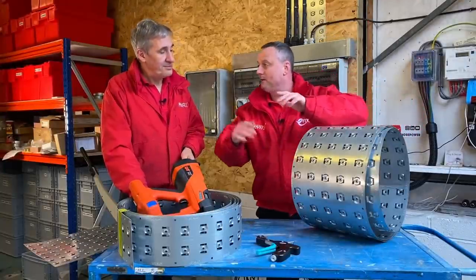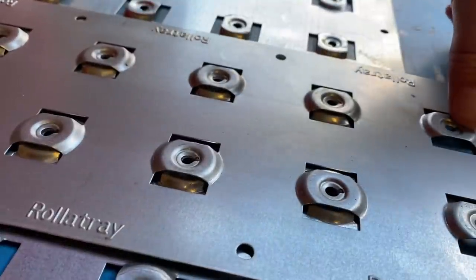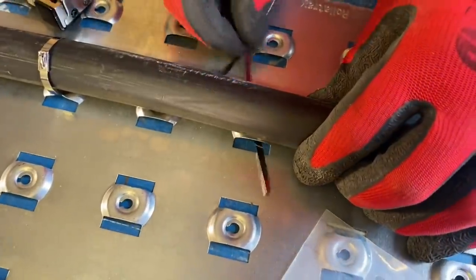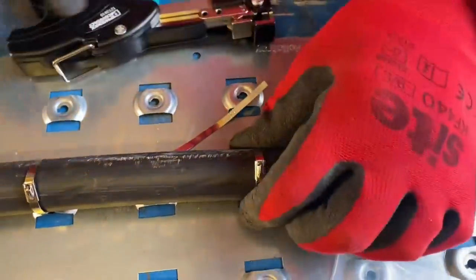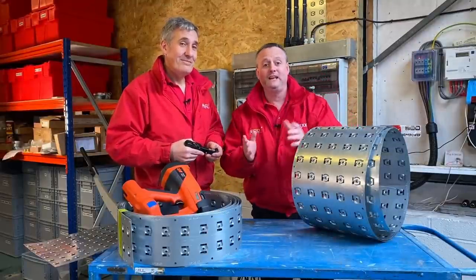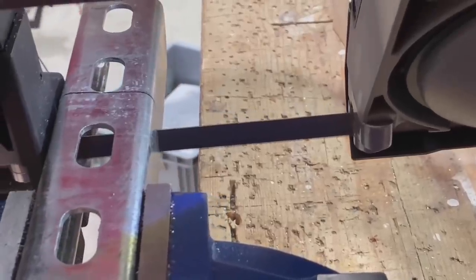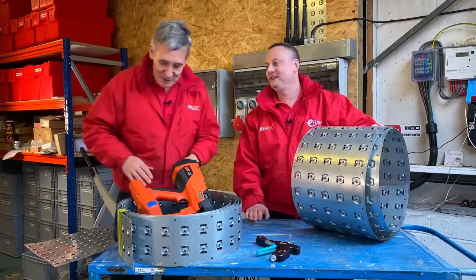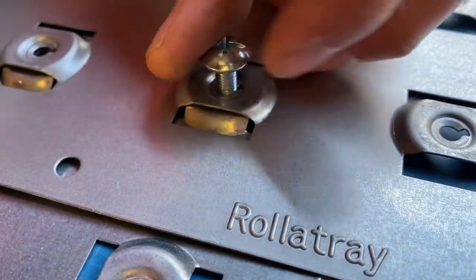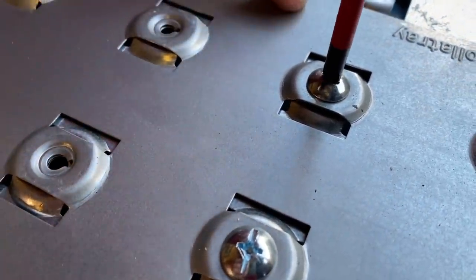When you're in there and need to change direction, you lay one on top of the other. There's a 6mm bolt that you send through to fix the two together. The indents in the tray itself have two functions: one is to put your cable ties around there like you would on a traditional tray. The shapes tessellate together - like Tetris - and you simply put a 6mm bolt through. It's not self-tapping; it actually uses the preformed thread to lock them in the tray. Job done.